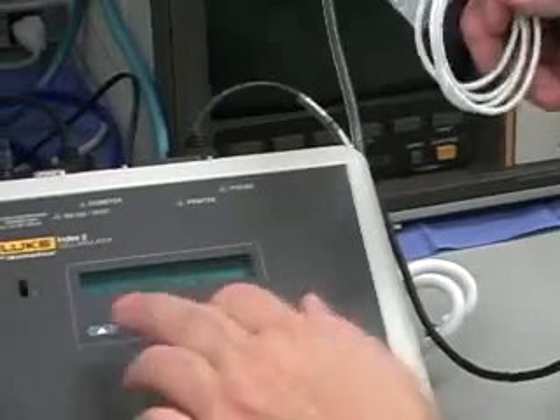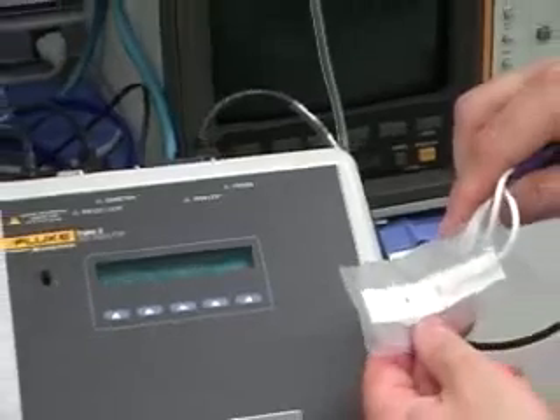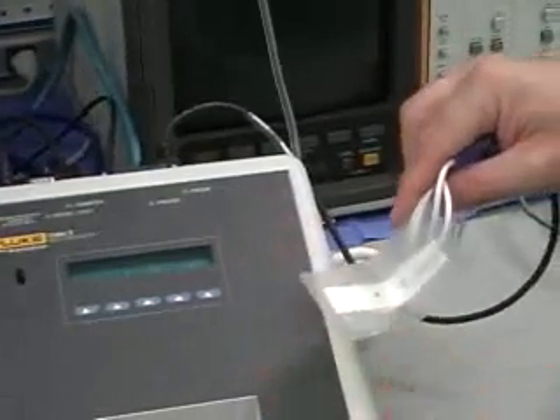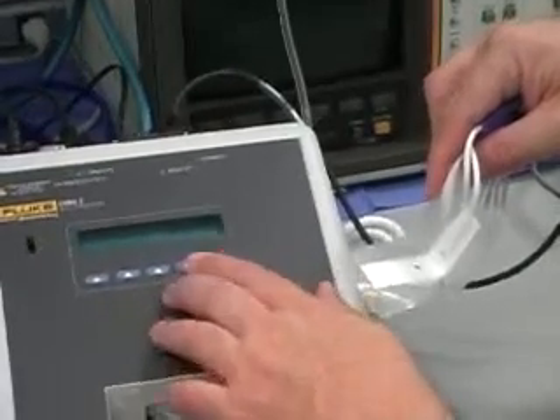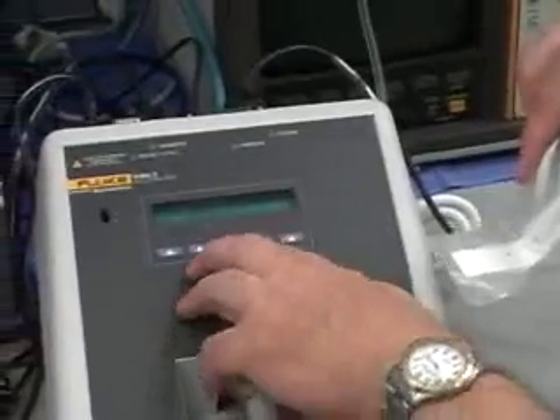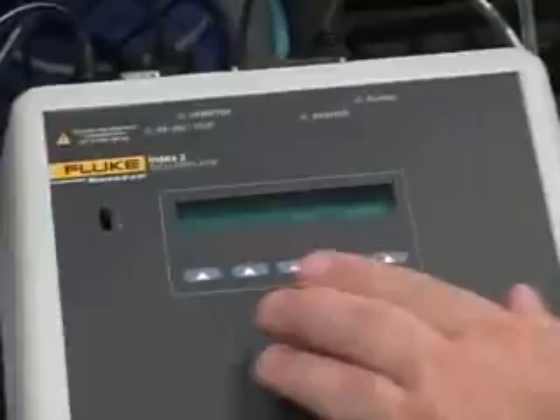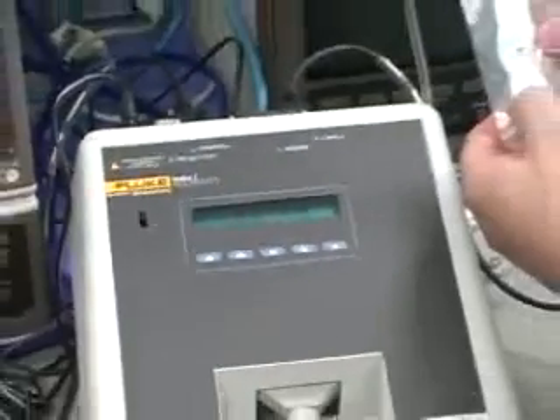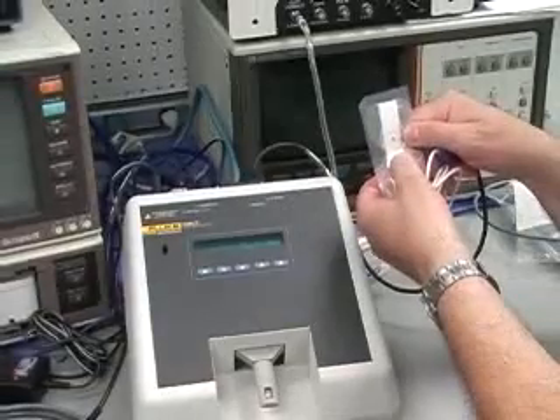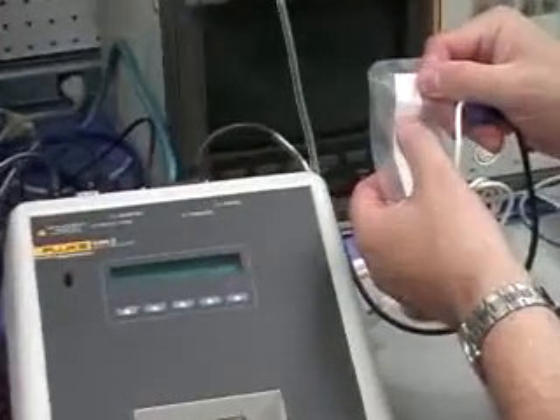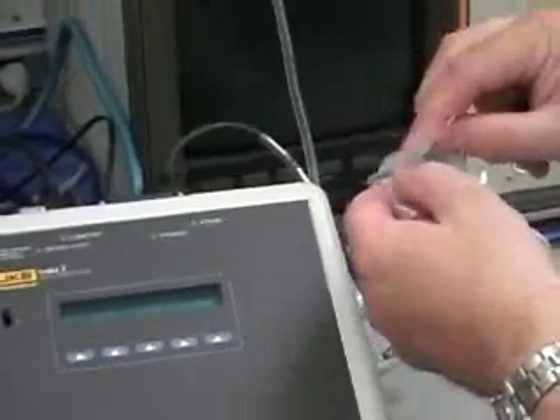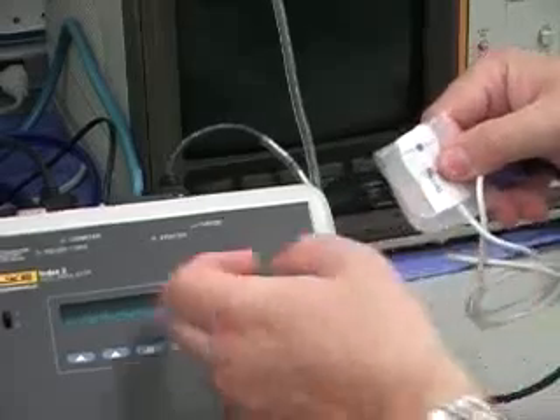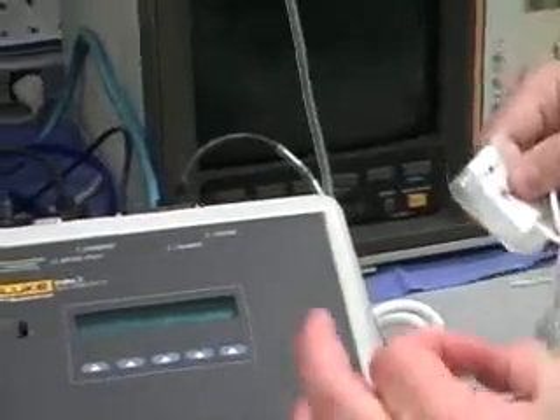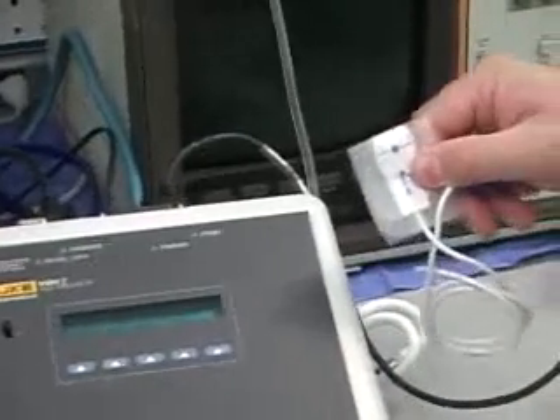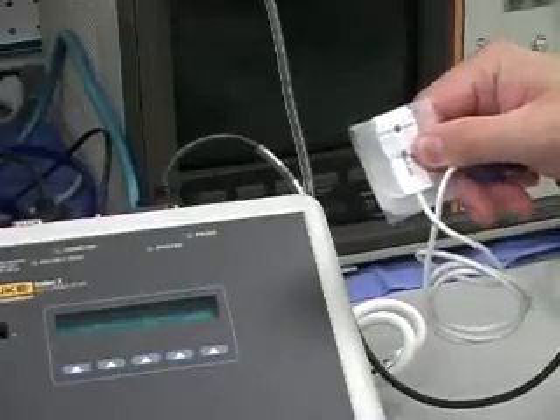Then two, you can actually bias the LEDs and the photodetector. In here there is a photo mode, and this is where you're actually pulsing the lights. We can see the visible red, but not the infrared. And we're also monitoring how much is getting to the photodetector on the other side. If you put them closer together, of course the numbers go higher. With these, we're going to include a piece of acrylic plastic so that you can run this kind of test with an optical load. But typically, numbers over 2,000 mean you've got a good probe.